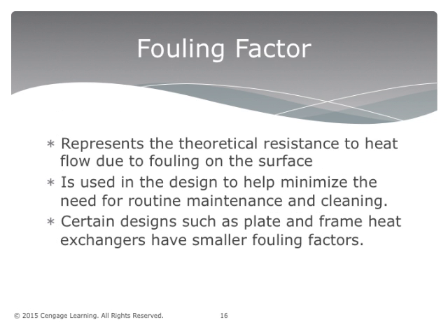The fouling factor is added to the overall heat transfer coefficient in order to compensate for the fouling that occurs on pipes or other surface areas. It is the buildup or accumulation of material, such as calcium or rust, that may occur naturally over time. Why is fouling a bad thing? Fouling on a surface is considered a resistance. Now, heat must transfer through this additional resistance, and depending on the application, we may not want that.